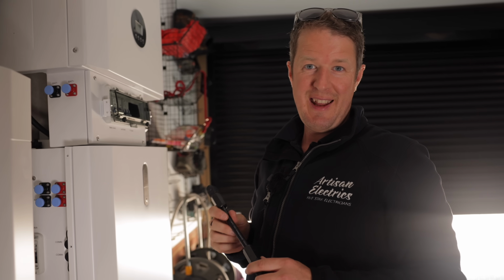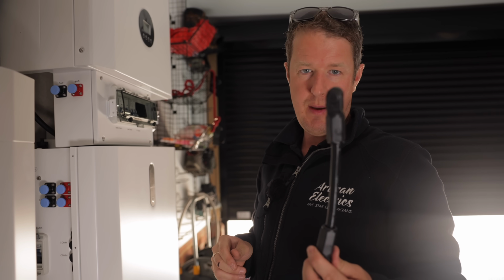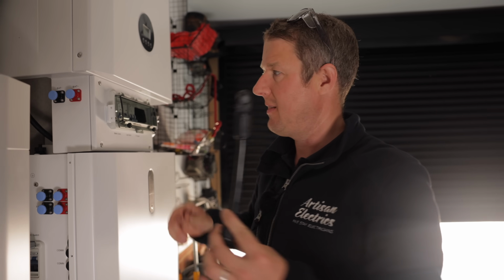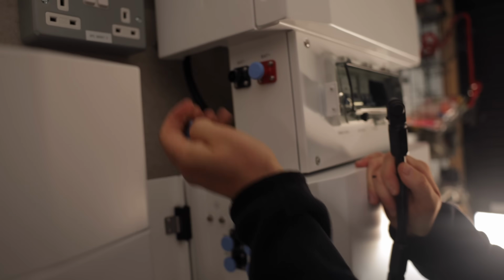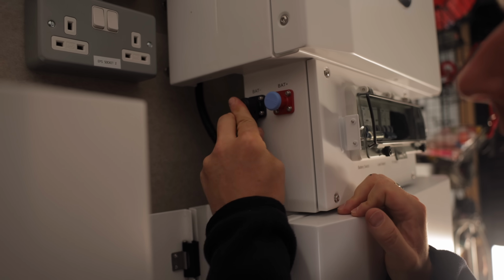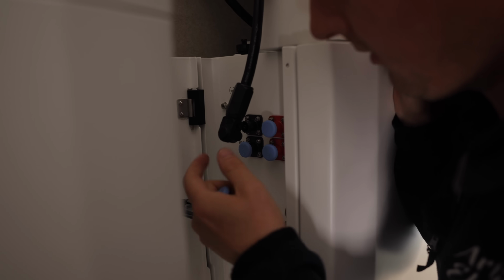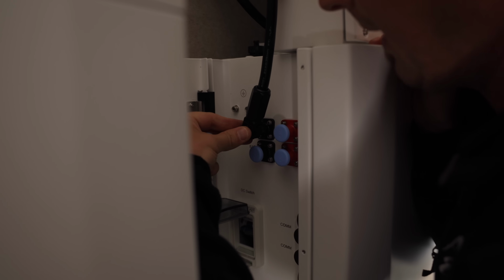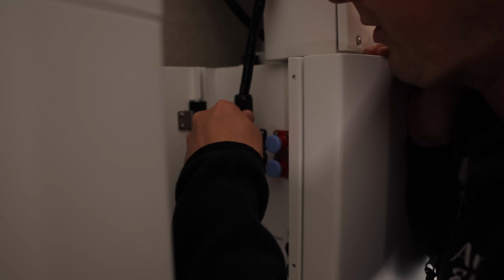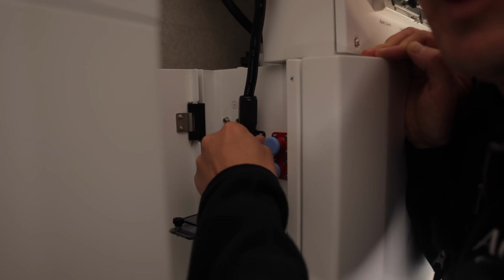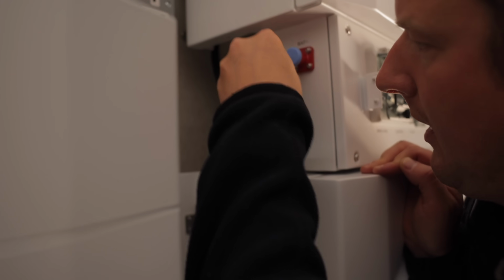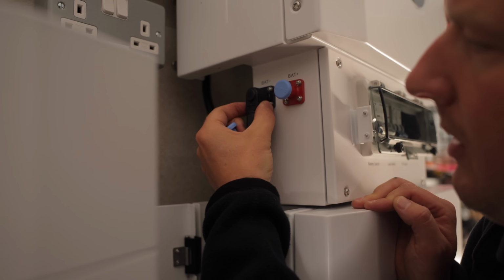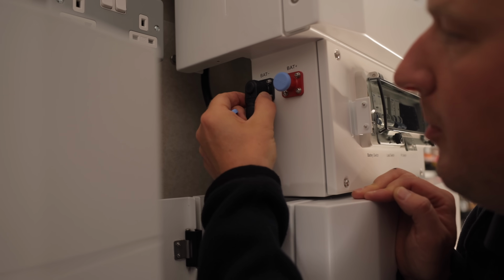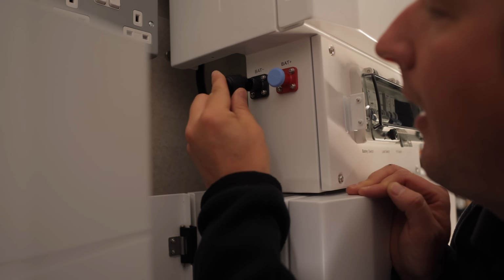Now it's time to connect the battery cables, starting with the power cables between the batteries. This negative cable goes from the inverter battery negative, pushed in until it clicks, then into the top battery negative of the top battery. The plugs need to be standing straight to go in, then they click - give them a little tug to make sure they're clicked in properly. To unplug them, there's a little button on the side you can push, then pull them out.